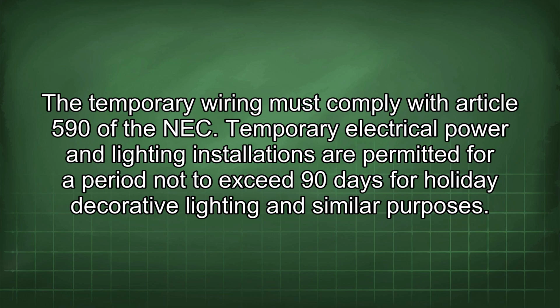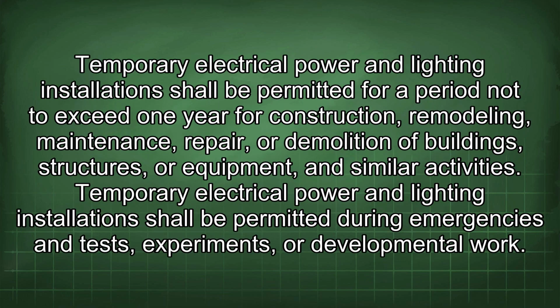Temporary wiring must comply with Article 590 of the NEC. Temporary electrical power and lighting installations are permitted for a period not to exceed 90 days for holiday decorative lighting and similar purposes. Temporary electrical power and lighting installations shall be permitted for a period not to exceed 1 year for construction, remodeling, maintenance, repair, or demolition of buildings, structures, or equipment, and similar activities. Temporary electrical power and lighting installations shall be permitted during emergencies and test experiments or developmental work.